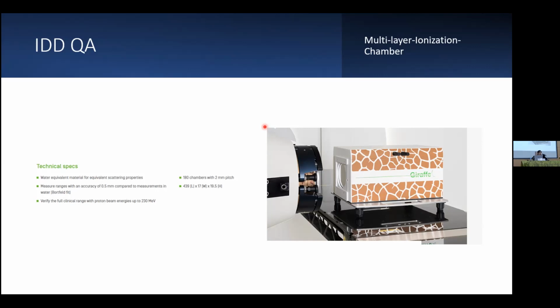The dose monitor was acting a little bit funny. So, okay, fine, good. I had the vendor come in to correct it. They did what they needed to do, and all was good. They did their beam test, everything else, and everything looked good. But then they wanted to be done. And I said, wait, we've got to do a few things. You actually went in and took all these things off and put them back on. I want to check and make sure that things are right. So I wanted to check the beam profiles and the depth doses. On that one, I did a more simplified measurement than this. But the key on that one is the vendor forgot to put something back in. And it wasn't a safety thing. It wasn't anything else. It was just a protective film.